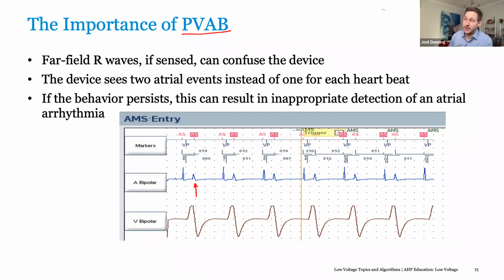This can essentially lead the device to, in this case, it said AMS, but it senses this as an atrial arrhythmia when this isn't an atrial arrhythmia. This is just a functionality of improperly programmed PVAB. So had this device had a proper PVAB, when this ventricular event occurred, either V pace or V sense, it will blank for a period of time, which will miss the atrial event being oversense here, and the device will no longer count this. So basically what we're doing with PVAB is we're trying to obscure what's happening in the ventricle on the atrial channel to avoid inappropriate mode switching.